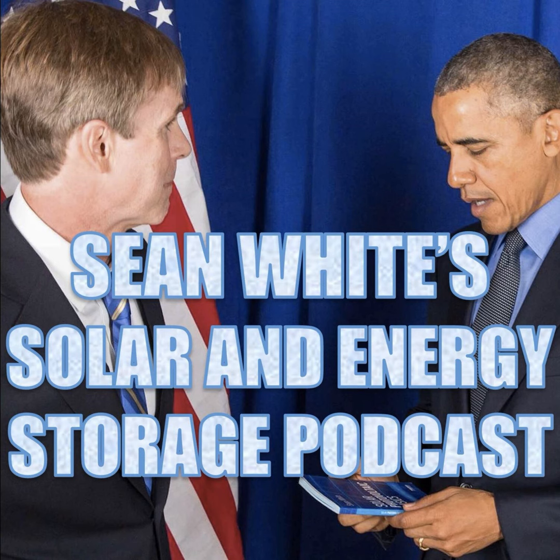So if somebody in Australia wants to buy an inverter with grid forming functions, you can sell them that. Yeah, we definitely can. In fact, Fluence was one of the first to bring to market something we call Ultrastack, which is for the TSO market -- the transmission system operator responsible for making sure the grid is stabilized and healthy. We have a couple of projects implementing our Ultrastack product in the EMEA market. It's really fast response, a lot of energy deployed when necessary to stabilize the grid, with a lot of advanced applications on top of these specialized inverters starting to come out.